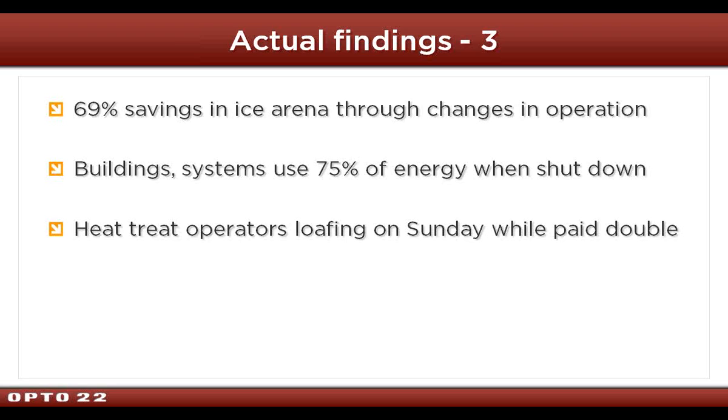They were spending $140,000 a year. They were only open 8 months a year. They were about to close. We put in instrumentation, started tuning the system. We dropped their utility costs from $140,000 for 8 months to $40,000 for a 12-month operation. This project actually received a DOE award for energy innovation. So we saved almost 70% in a project that already had made capital improvements, and they were all changes in operation and maintenance.